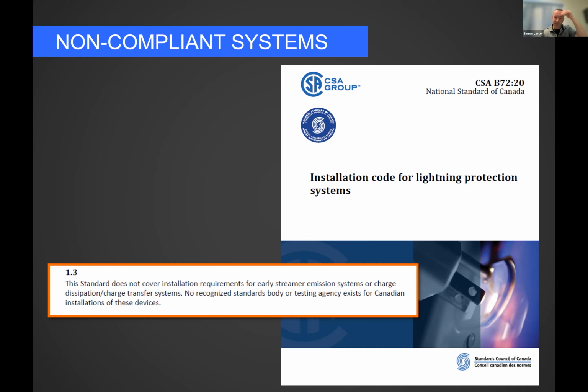Main-sized cable, ground loop conductors. So do you have to bond to the ground or to the gas line? Are you guys bonding to the gas line in all cases? Because we bond to the gas line in the electrical code, we have to bond to the gas line. So do you bond to it as well? Yes, yeah, we do actually. That's the way NFPA 780 is written, and that's the way now CSA is written. We have to bond to gas line, electrical, water pipe.